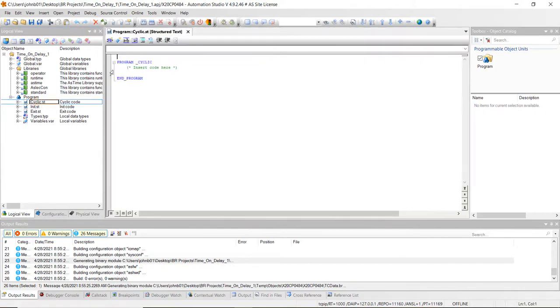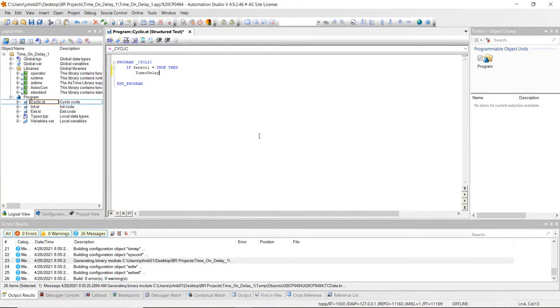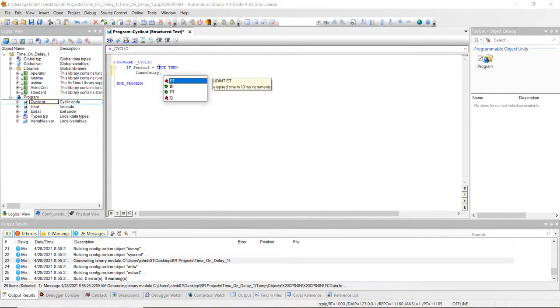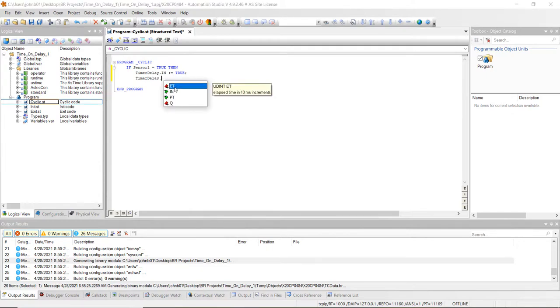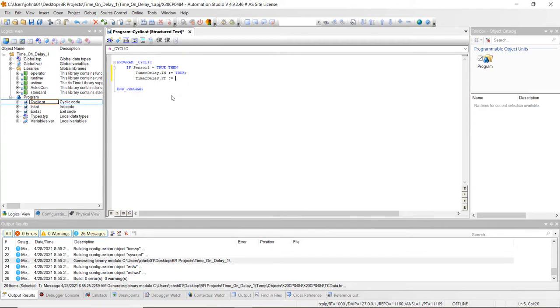Next, open up the cyclic and we're going to insert the code for this program. We're going to say: if sensor one equals true, then we want to set timer delay dot IN to equal true, semicolon. Then we want to set the time for the delay — this is in 10 milliseconds — so we do timer delay dot PT. I'm going to set that to 100. That's not going to be 100 milliseconds; it's actually going to be 1000 milliseconds because this is a 10 millisecond timer — it counts in 10 millisecond increments, so 100 times 10.